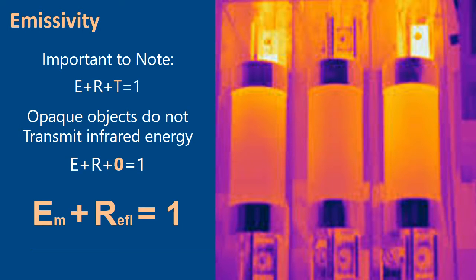There's an important relationship with the emissivity plus the reflection that equals one. So basically whatever you do to one will affect the other. They're linked. If I increase emissivity I decrease reflection. If I decrease emissivity I increase reflection. It's an important relationship that you need to understand when you start getting into infrared measurement, and it underpins why it's very important to do your training because these things are covered in much more depth.